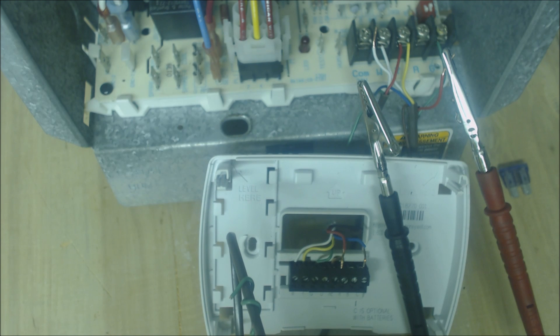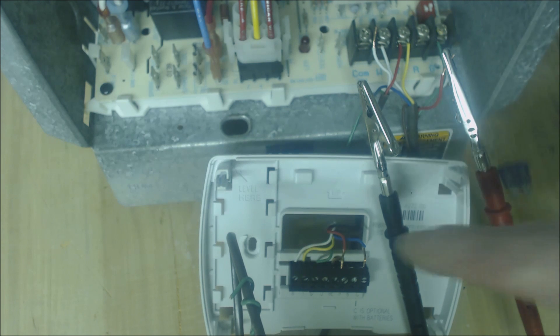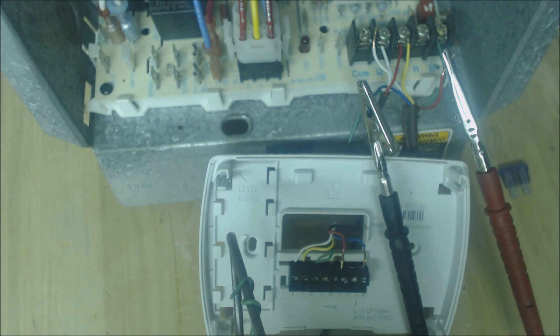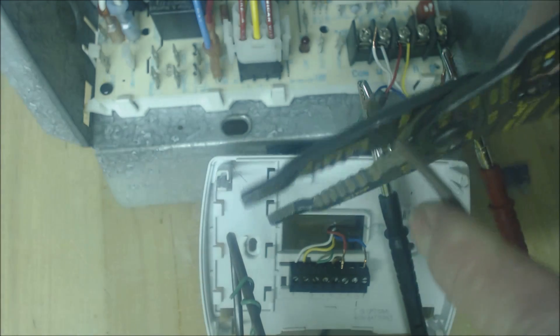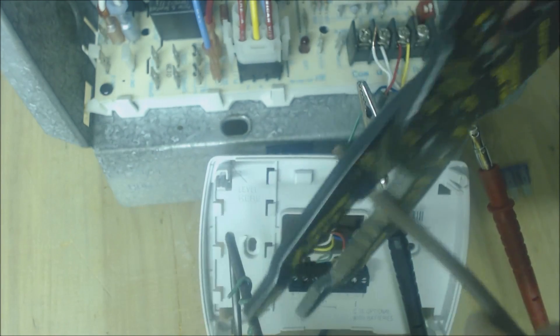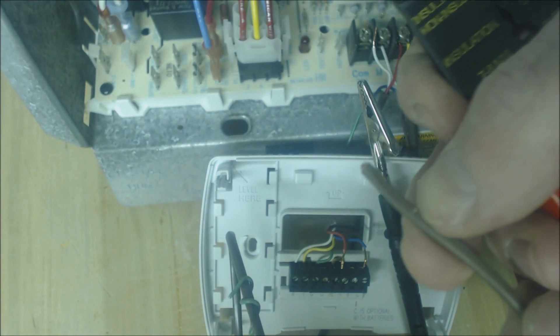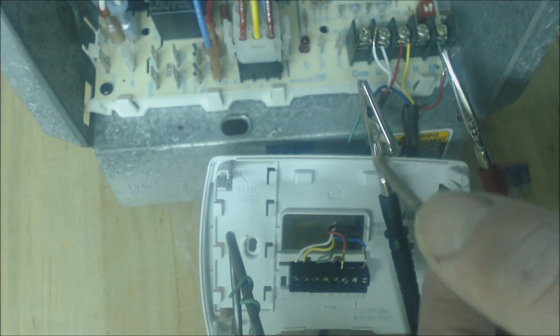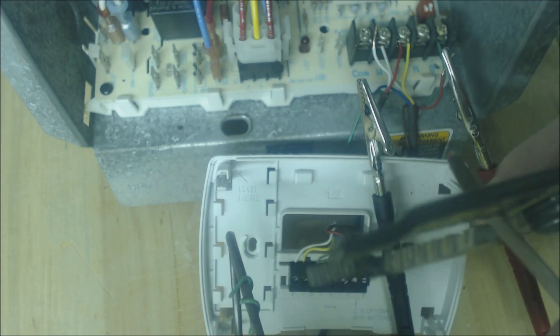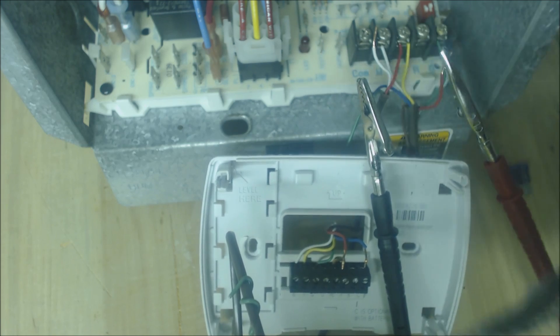Something that you can check for—you want to visibly check to make sure that the thermostat wire was not stripped in this way. You never want to have a thermostat wire that was stripped in this way because maybe nine out of ten times somebody might be able to just pull the brown sheathing off, but most of the time they will have nicked the thermostat wires.